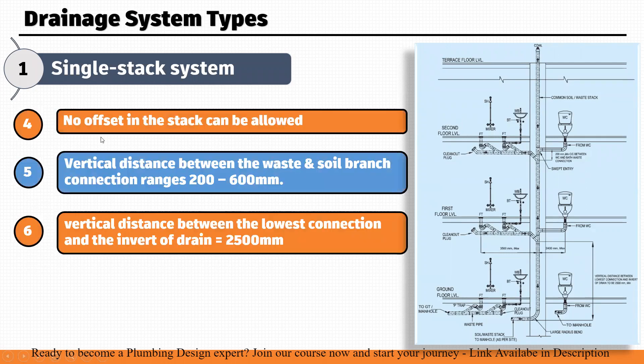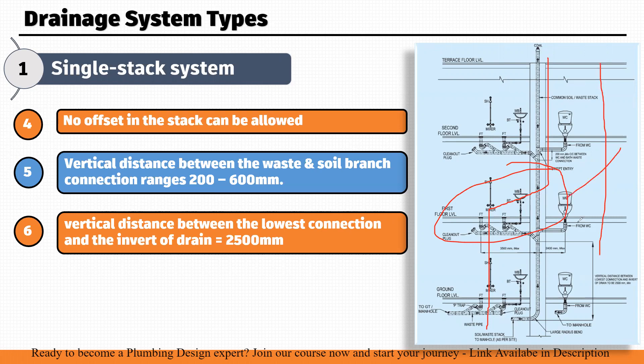The fourth point is that no offset in the stack is allowed. The pipe must run straight vertically. If there is a change in layout requiring an offset, you must take a separate pipe — no offset is permitted in the single stack.